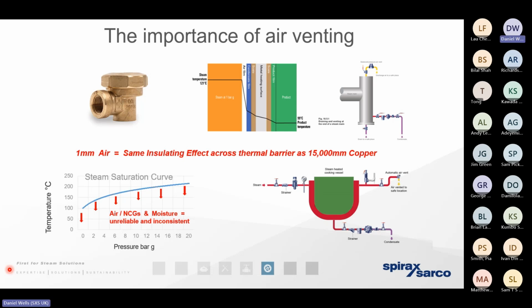So if you think about whenever steam's carrying air with it, when it condenses, the air becomes absorbed back into the condensate. That condensate becomes carbonic acid. That's what creates the corrosion. Boilers, they actually like alkaline water. So if we get acidic condensate back to the boiler house, we've got to consume more chemicals, and therefore our cost of steam increases.